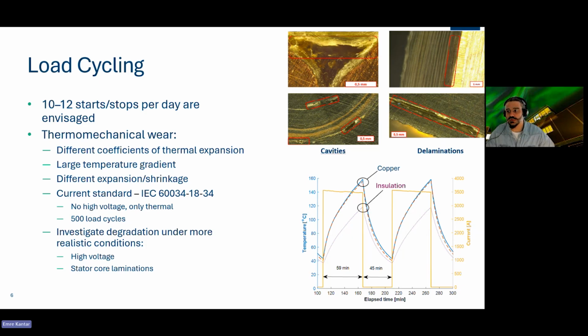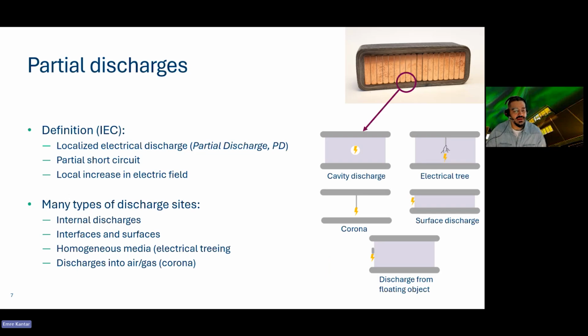But to make it more realistic, because in real life machines, while they are being exposed to these thermal gradients, high voltage is also present, right? So we thought this thermal cycling should be done in the presence of high voltage. When there is high voltage present while these cavities are being formed, there are localized electrical discharges called partial discharges happening in those small cavities or delaminations. The bigger the cavity, the lower the service voltage at which you can get these discharges. And if these discharges persist for a long time, they will degrade the insulation.